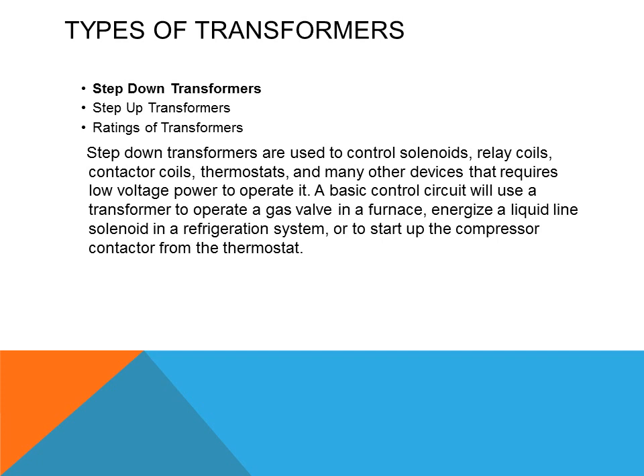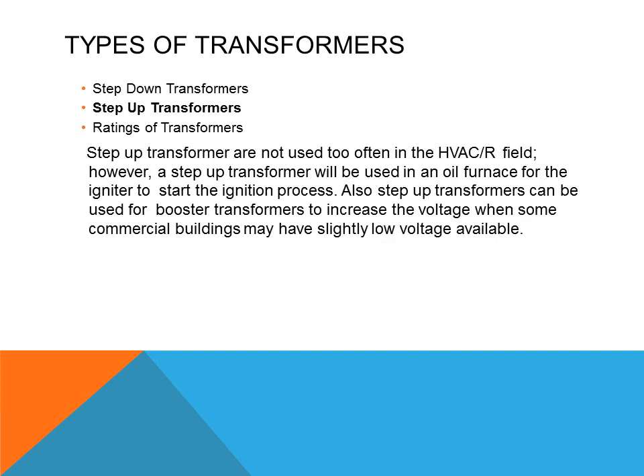Step-down transformers are used to control solenoids, relay coils, contactor coils, thermostats, and many other devices that require low voltage. A basic control circuit uses a transformer to operate a gas valve in a furnace, energize a liquid line solenoid in a refrigeration system, or start up the compressor contactor from the thermostat. Step-up transformers are not used as often in the HVAC field, but are used in oil furnaces for ignition and as booster transformers in commercial buildings with slightly low voltage.